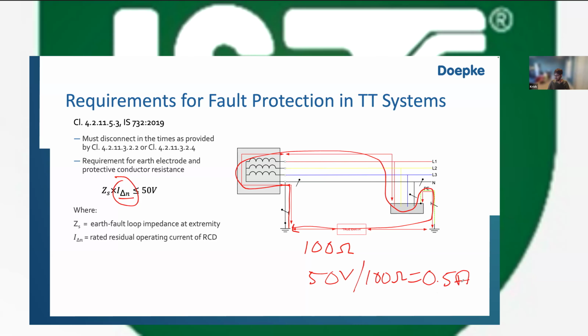So if this was the case, for example, this was the way to do it. Another way of looking at it is that we know that your I delta is 300 milliampere in this case. So 50 volt divided by 300 milliampere, which is 0.3 ampere. So 50 volts divided by 0.3 gives you a value of about 167 ohms. So if your fault loop impedance in the system is lesser than 167 ohms, then 300 milliampere can be used.